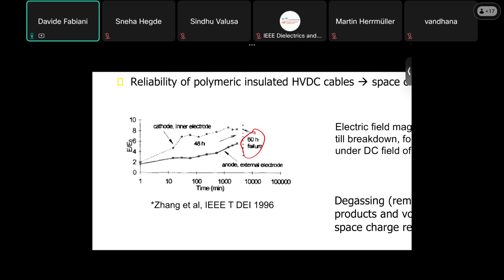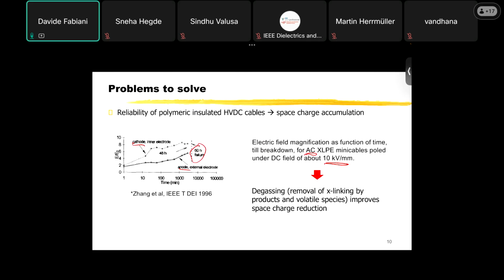And the reason for that is that the electric field at the cathode and at the anode, so at the electrodes of the cable, increased a lot during the polarization, the application of the voltage. Under AC, the electrical insulation is not so critical. The XLPE used for AC had a lot of cross-linking byproducts. And these cross-linking byproducts, if you apply electric field, create ionic species that can migrate to the opposite electrodes, creating space charge accumulation.